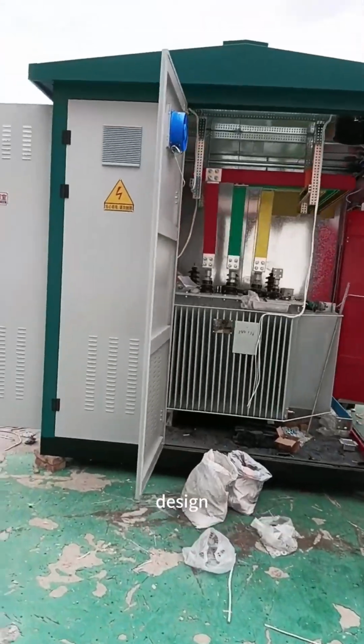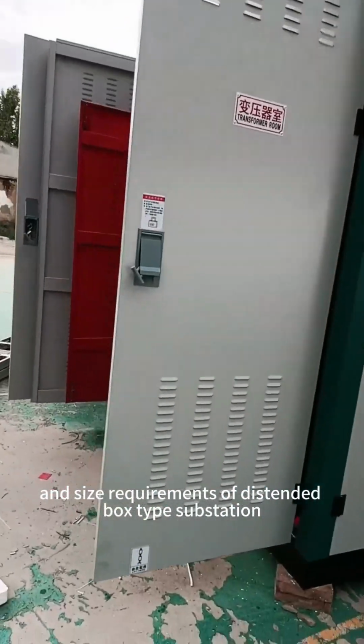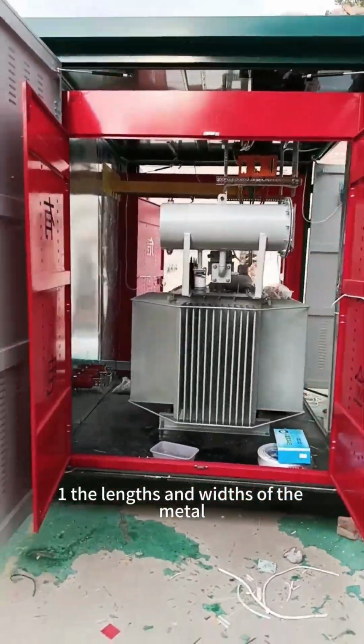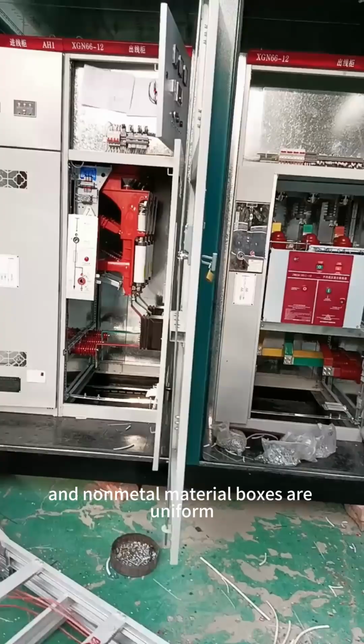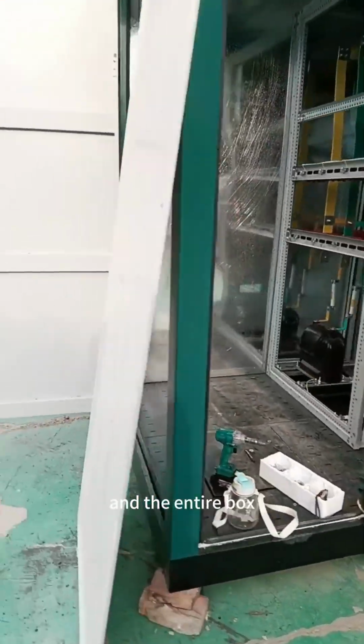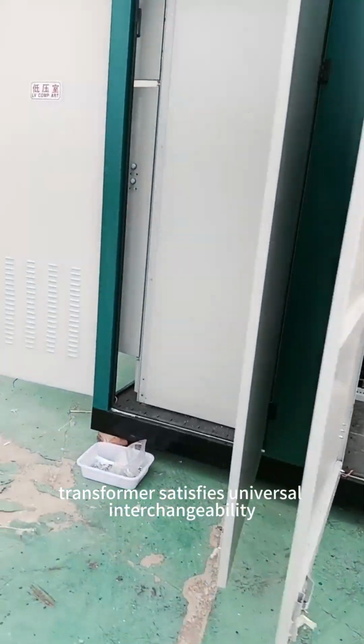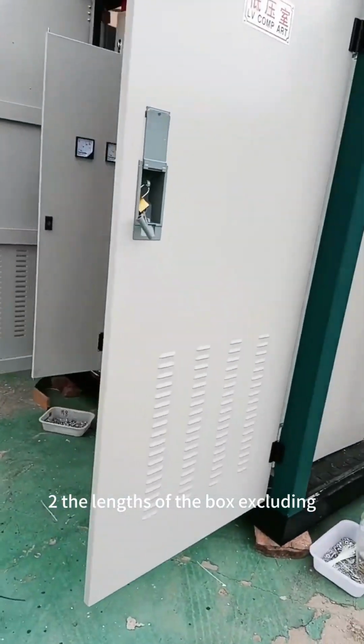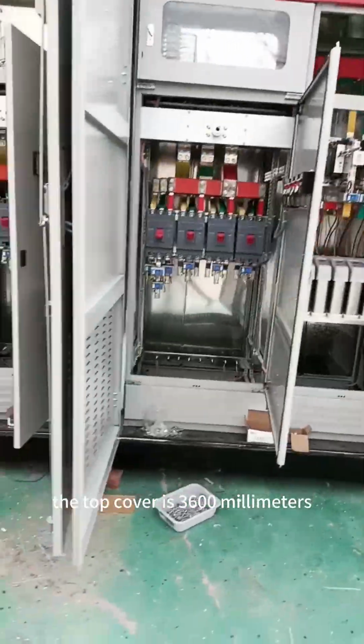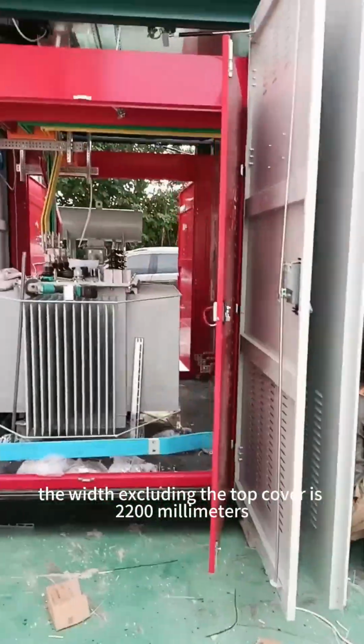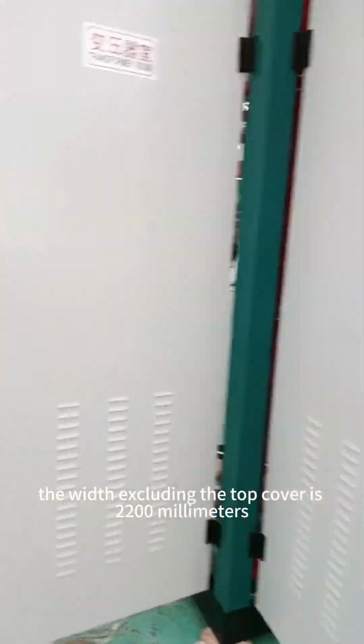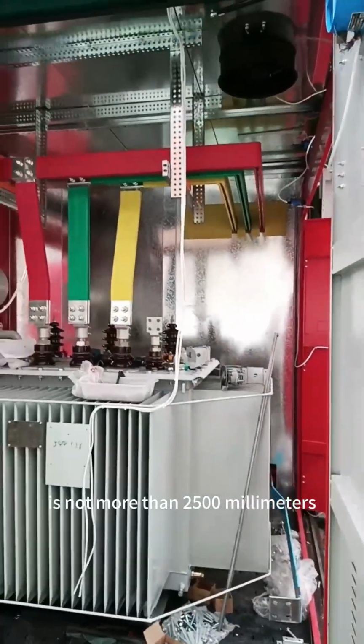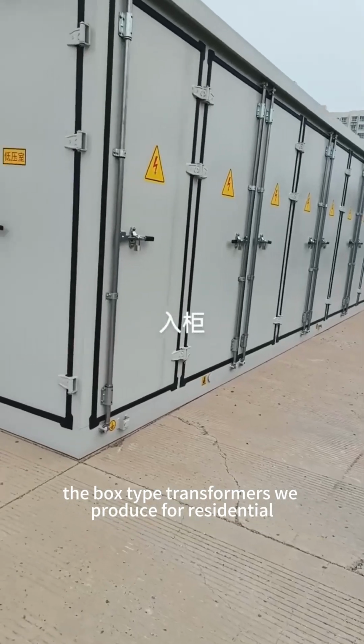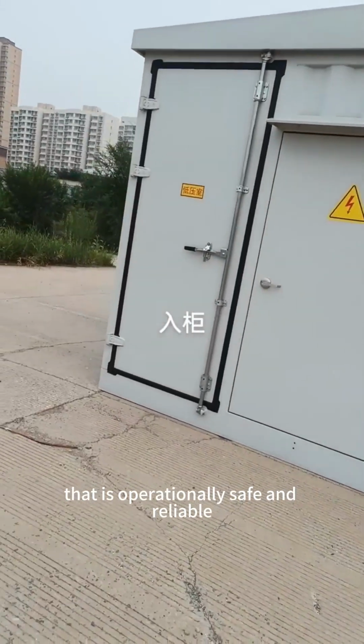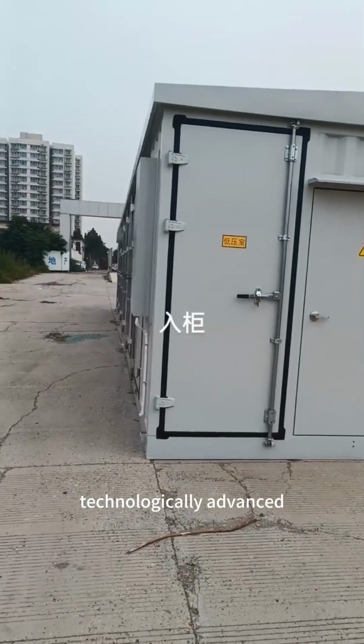The typical structural design and size requirements of the standard box-type substation are as follows. The lengths and widths of the metal and non-metal material boxes are uniform, and the entire box transformer satisfies universal interchangeability. The length of the box excluding the top cover is 3,600 millimeters, the width excluding the top cover is 2,200 millimeters, and the height excluding the top cover is not more than 2,500 millimeters.